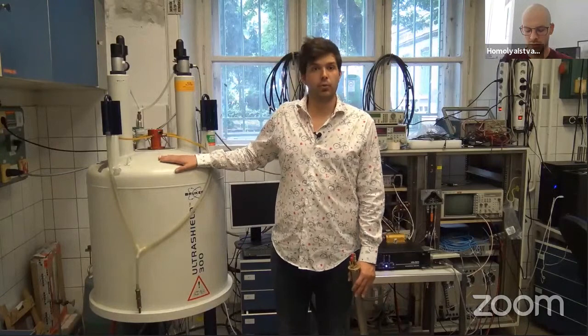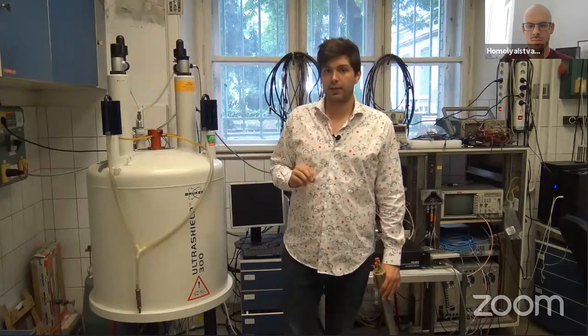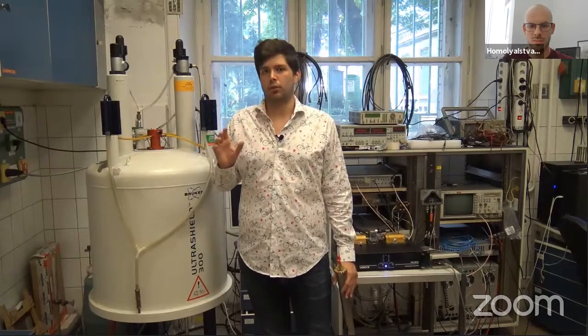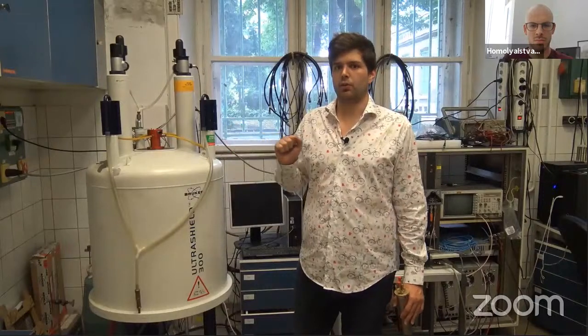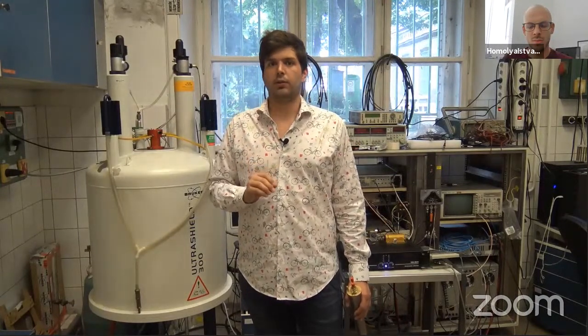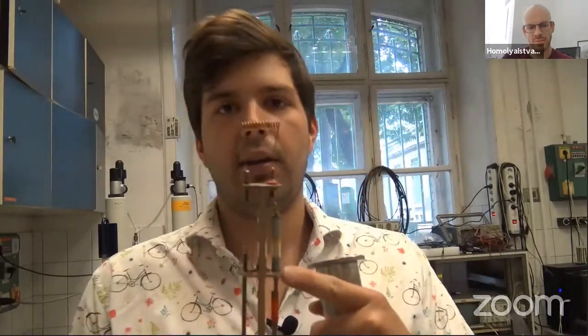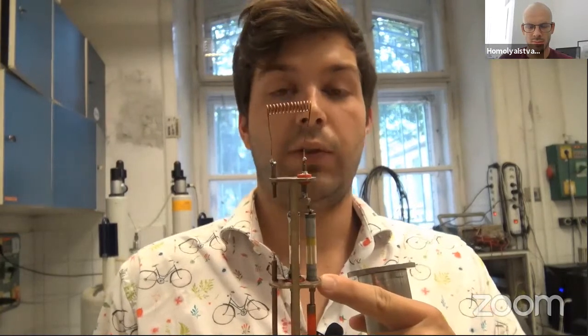The small nuclear magnetic moment of protons is aligned with the high magnetic field produced by the superconducting coil. However, if we somehow tilt the magnetization of the protons, then the magnetic moment of protons starts to spin around the magnetic field produced by the superconducting coil with a frequency of 300 megahertz. This is the so-called Larmor frequency. Just like the children's toy, just a little bit faster. Such a spinning magnetic moment also induces a voltage in a solenoid coil. Interestingly, this solenoid coil is also the instrument we tilt the magnetization with. The solenoid coil is attached to two capacitors that we can use to match the frequency of the material we place inside the NMR.